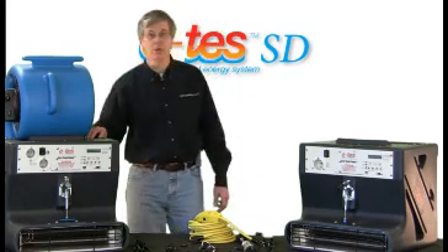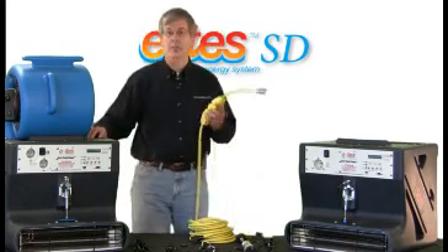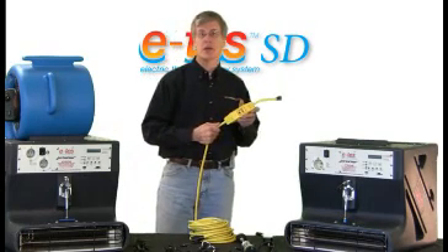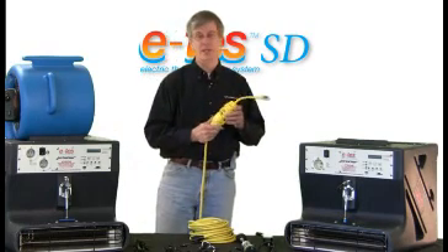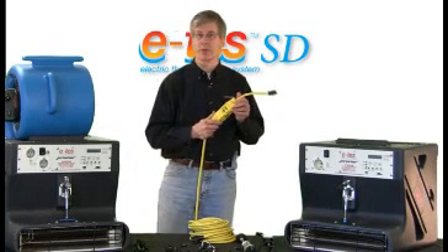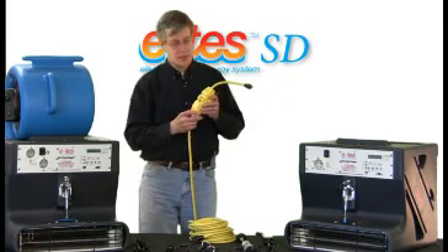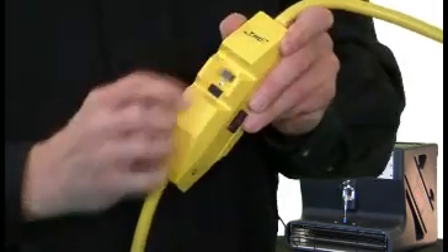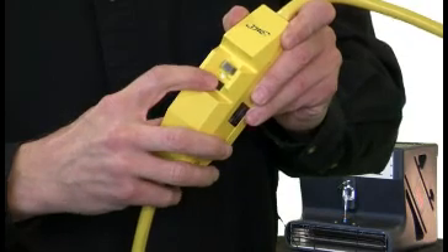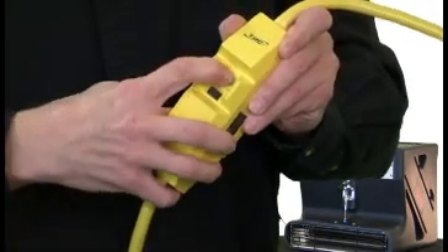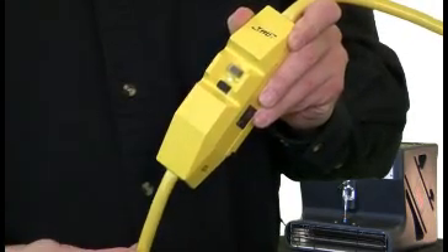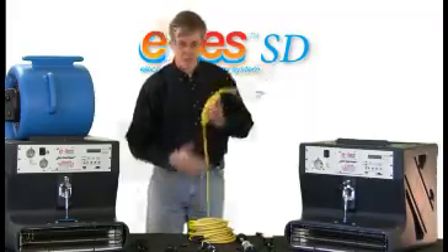First thing we want to go over is the power cords. Each power cord for our E-Tes SD units has a ground fault circuit interrupter. When you plug the unit in the wall, you will push the button on the front to set the GFCI, then test to make sure that it pops, reset it, and you're ready to go.